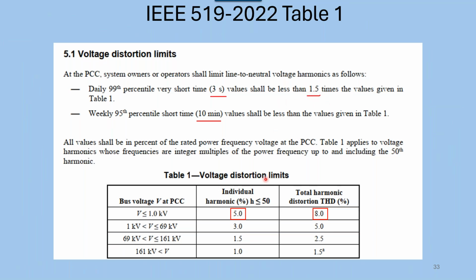So here's table 1. Most of the systems that we are involved in are 480 volts. So the individual harmonics have to be less than 5%, and the total distortion, THD, has to be less than 8%. So when we look at the chart that I'm going to show, you'll see 8 and 12. 8 is going to be the 95 percentile, 12 will be the 99. So these are where the voltage limits are. Okay? Any questions?